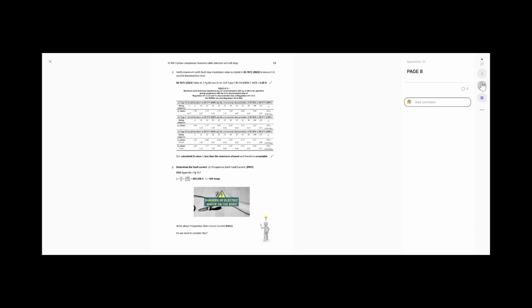Right. So to confirm that, we're also going to look at calculating the fault current. And by fault current, I'm going to expand a little bit more than we did last week. When we're calculating fault current from this point, we're using our Uo value, our voltage to earth. So this is our prospective earth fault current value that we're calculating. Again, we can find it in Appendix 3 of the On-Site Guide, and it gives us a formula. So to calculate our fault current, If, we need to divide our nominal voltage, 230 volts, by our value of Zs to get a fault current value. And again, it's just Ohm's law. So our fault current, based on our 0.57 earth fault loop impedance, is 403.508 amps. In other words, about 404 amps of current that would flow if you had an earth fault.